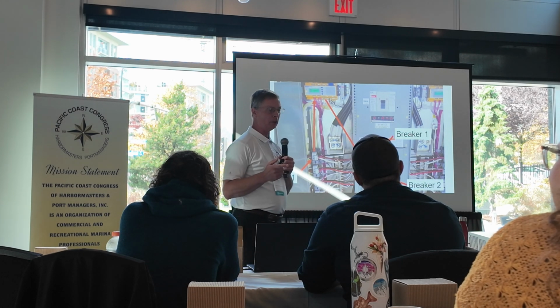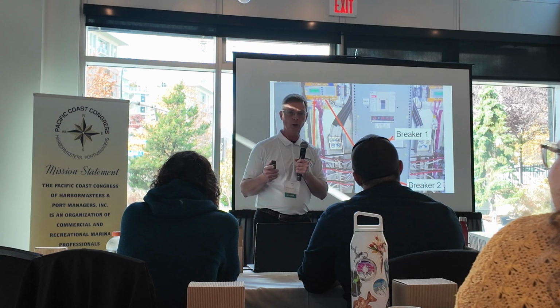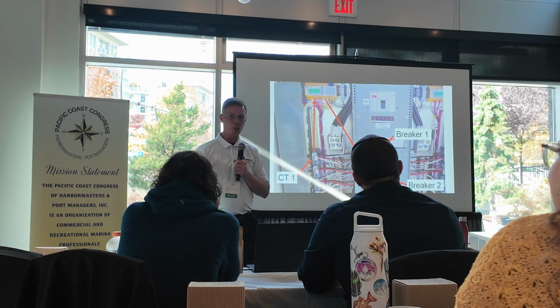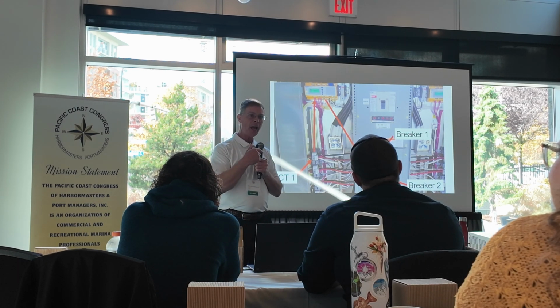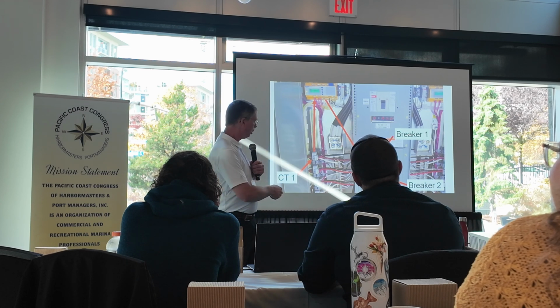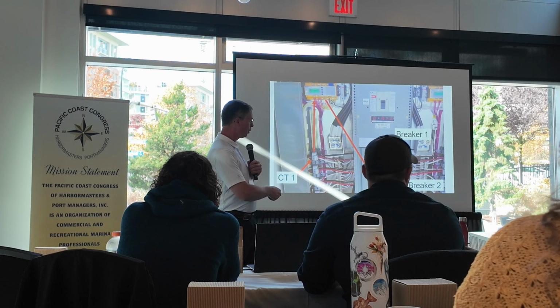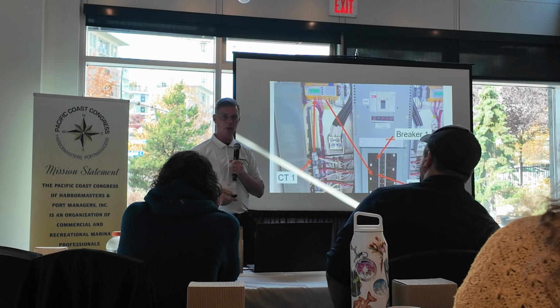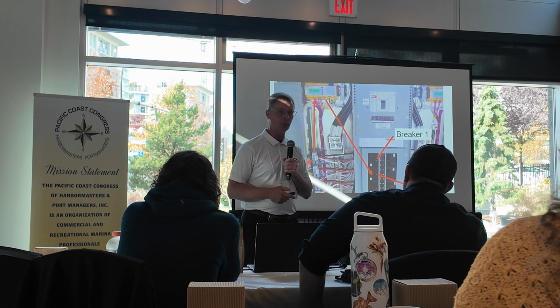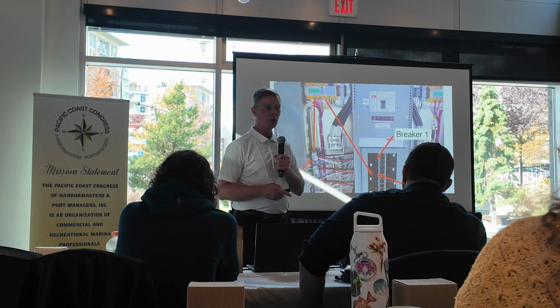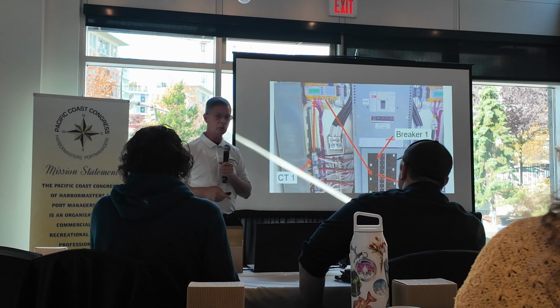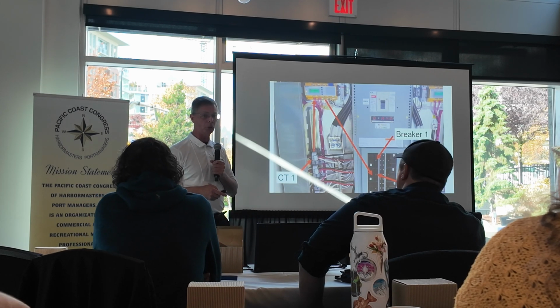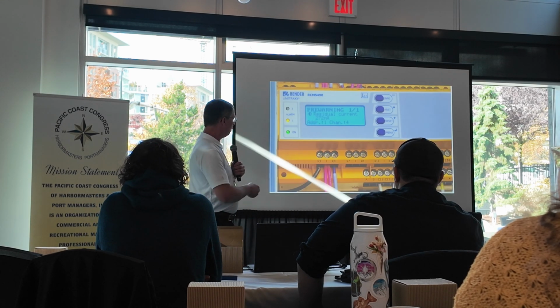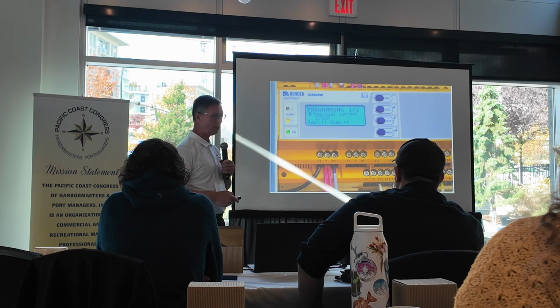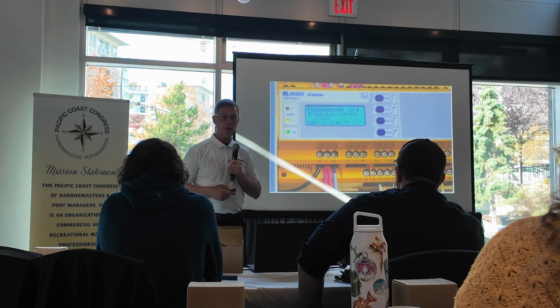And actually there was an electrocution that occurred, not on this project, but another project, where this actually happened, and leakage current was coming from here, but it tripped the wrong breaker, and actually there's an individual that is deceased now because of this. So these are not just random things, these are actual cases that are major issues. So that's a problem. And you can see I was leaking up to 272 milliamps of leakage current on that circuit and it wouldn't trip.